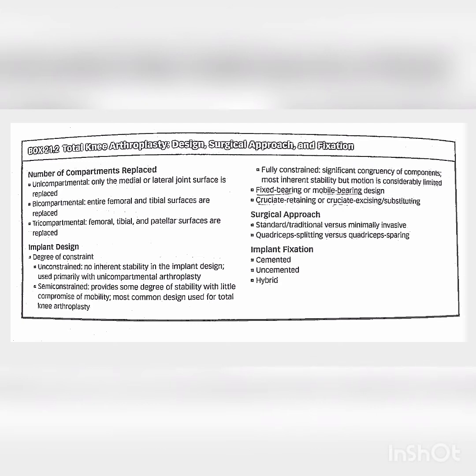TKA designs are also classified as mobile bearing or fixed bearing. A mobile bearing knee has a rotating platform inserted between the femoral and tibial components, whose top surface is congruent with the femoral implant, but whose undersurface is flat for rotation and sliding of the tibial component. A fixed bearing knee does not have such an insert.